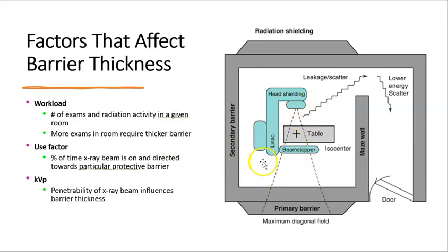Where is it angled? So if it's a dedicated chest room, this wall would get a ton, right? If it's 60 exams a day compared to 5 exams a day, that's going to be a huge factor in our workload and our use factor, okay?